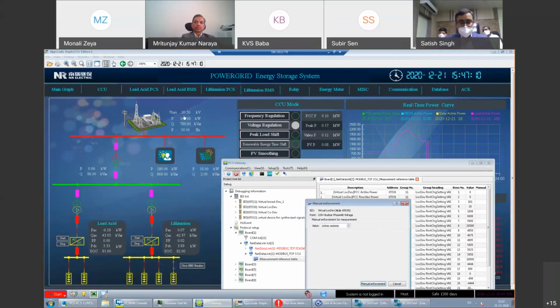For example, let us go beyond the band and try to set the voltage regulation value to say 20.5 instead of the existing value, and see how the battery is responding. We see there is reactive power support to the grid whenever the voltage is manually forced to 20.5 kV. Similarly, can you please set another value beyond that, maybe 23.5 would do. Once we set the value and there is an over voltage condition, the battery is absorbing reactive power.